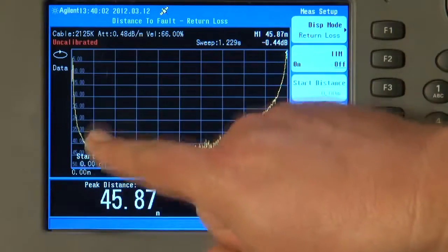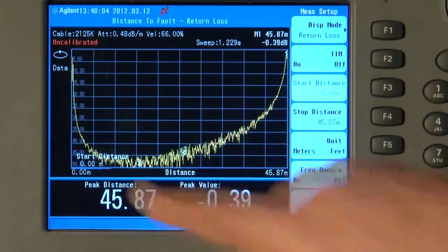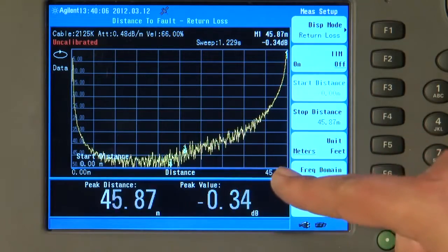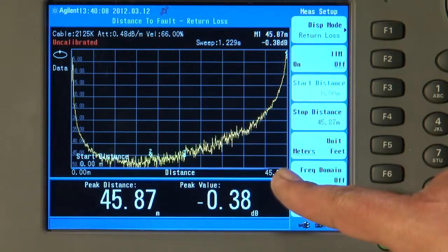The Y axis still shows return loss in dB, but the X axis now shows distance to fault in meters, or in feet if you prefer. We need to tell the instrument approximately how long the cable is. This will optimize the measurement and avoid unnecessarily testing beyond the end of the cable. If you are new to making distance to fault measurements and are not familiar with Fourier transforms, be aware that the frequency span you are sweeping directly influences the maximum distance you can measure and also how accurate you can resolve the distance to faults.